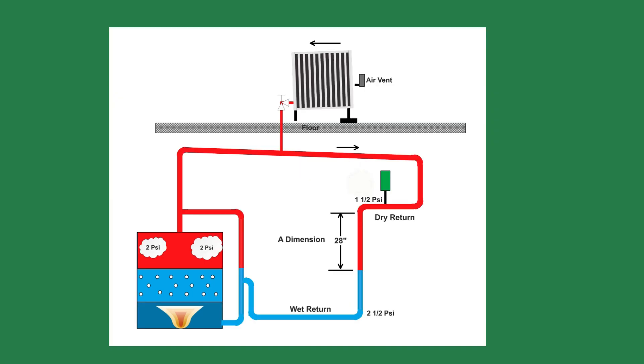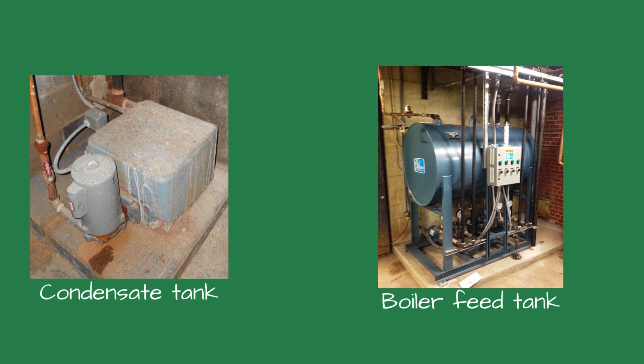In a residential steam system, the condensate is returned to the boiler by gravity and leftover steam pressure. Commercial systems require a mechanical method of returning condensate to the boiler because the building is much larger than a home. That job falls to either a condensate or boiler feed tank.